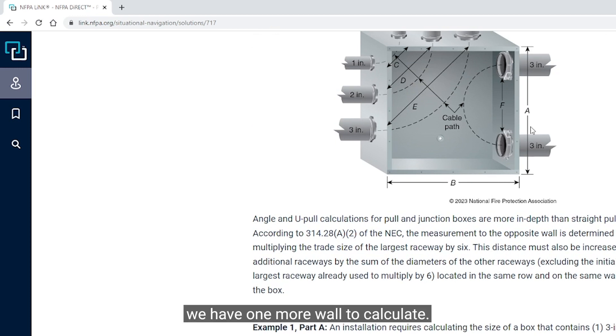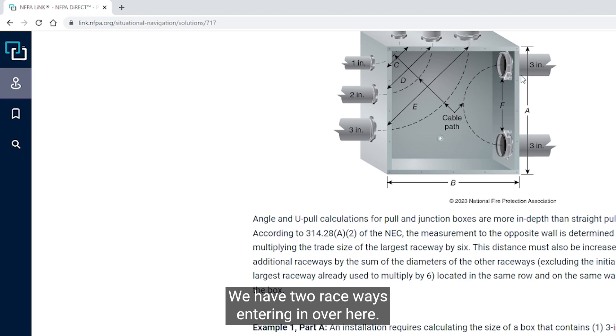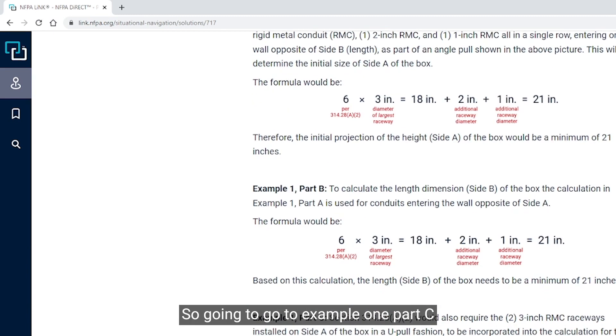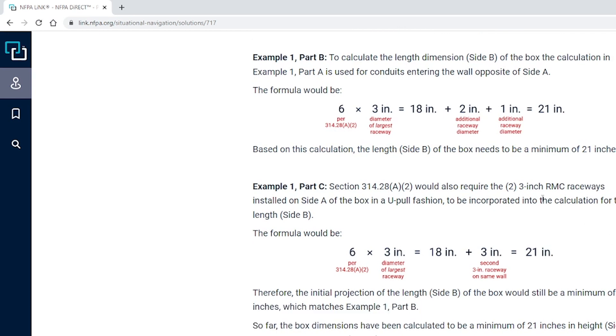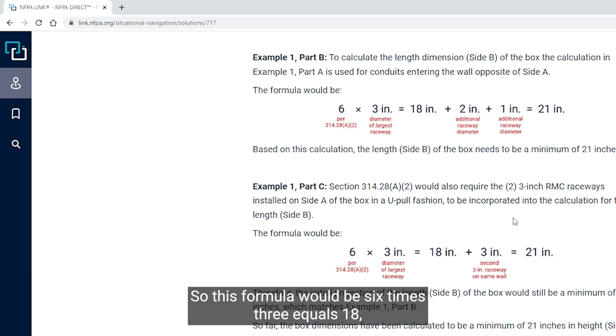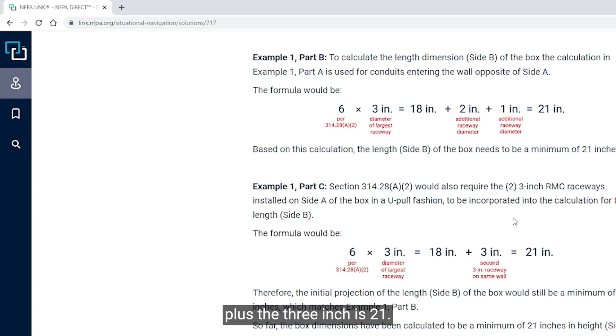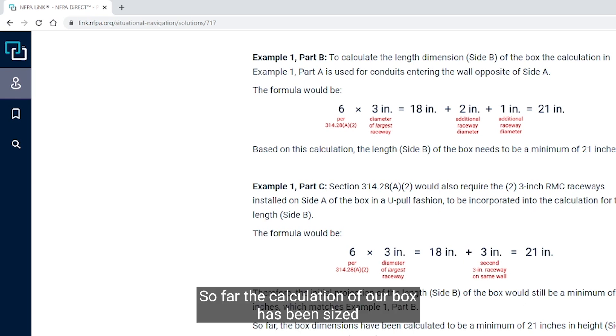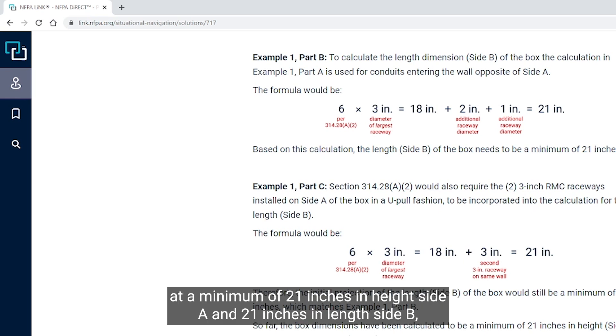To calculate the length dimension, which is side B of the box, the calculation in Example 1 Part A is going to be used for the conduits entering the wall opposite of side A. That, again, would be 6 times 3 equals 18 plus 2 plus 1 for 21 inches. So currently for side A and for side B, we have a 21 by 21. We have one more wall to calculate. We have two raceways entering in over here, so I'm going to go to Example 1, Part C.